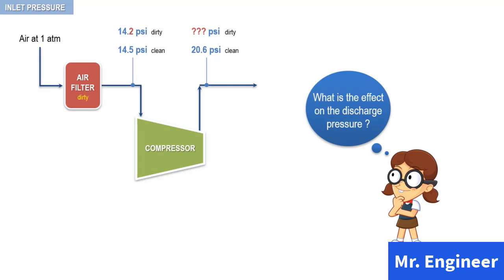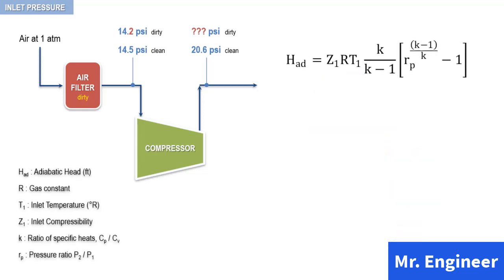For a centrifugal compressor, discharge pressure is related to the adiabatic head according to the following equation. Here, Z1 is the gas inlet compressibility, R is the gas constant, T1 the gas inlet temperature, K is the ratio of specific heats, and RP is the pressure ratio of the gas — that is, the discharge pressure divided by the inlet pressure. In this equation, subscript 1 refers to the compressor inlet, or the compressor suction.